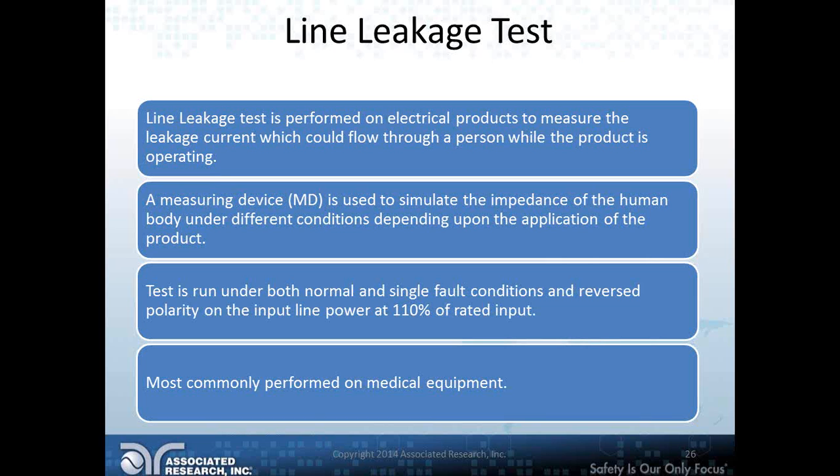And line leakage test is most commonly performed on medical equipment. However, there are other standards that also call out for a line leakage test to be performed on some different types of products. But the medical industry is basically the biggest user of line leakage testing.